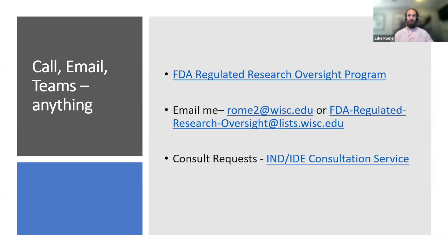If it also involves an investigational device that is potentially significant risk, then you might also need to have a submission to the FDA related to that device. In those cases, it's possible to talk to the FDA to see if you can submit the entire protocol under either an IND or an IDE instead of trying to break that out into two separate protocols. It also gets into issues of, is it some sort of combination product?